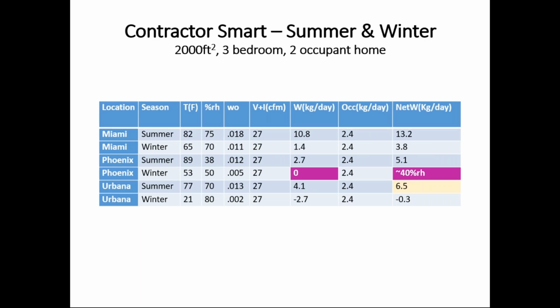And then finally, Contractor Smart, bringing in air as needed to manage air quality. Now we're getting down to about 13 liters per day during the average day in Miami summer, much, much less than 90 to 100. A huge impact on the home's energy, as we'll see, as well as making it much easier for equipment to manage this moisture load. Phoenix drops the indoor humidity in winter, comes up to about 40%. In Urbana, we see that we drop down to about 6 to 7 liters of dehumidification during the summer on average. And in the winter, essentially, we don't need to add any moisture to keep at 30%.